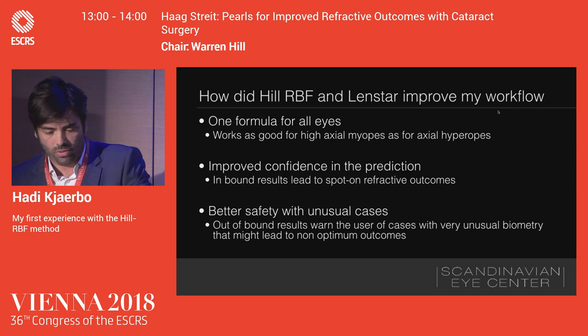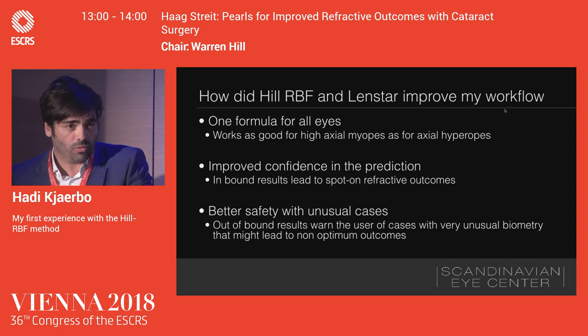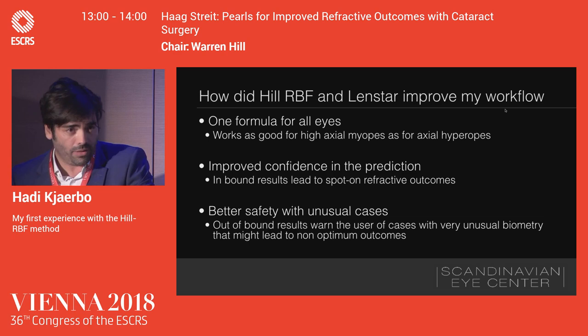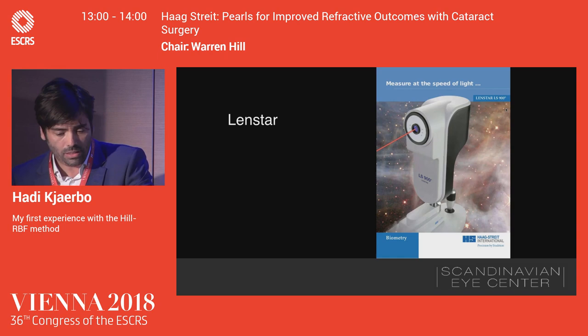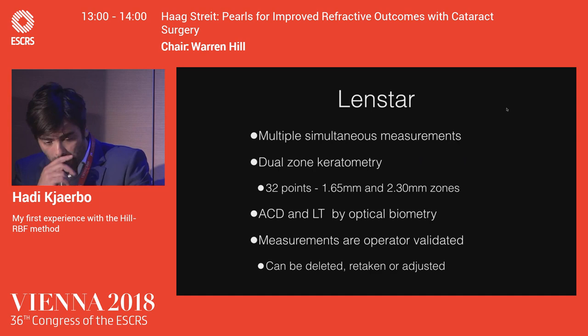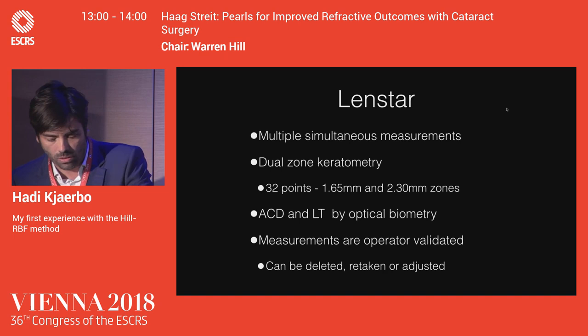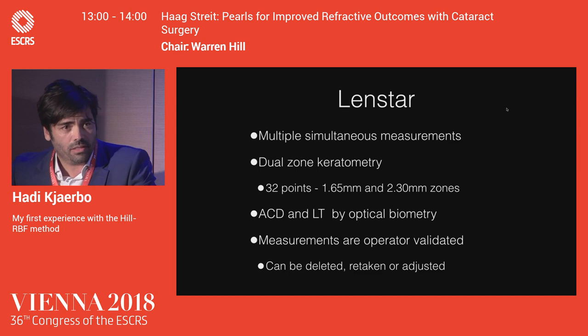How did the Hill-RBF and the LensStar improve our workflow in the clinic? Well, it's one formula for all eyes. We have improved confidence in the prediction. Inbounds results give us very good refractions. We have better safety because we can be more aware of the unusual cases. Regarding the biometer, I'm really happy using the LensStar. With one click, you get multiple simultaneous measurements. You have dual-zone keratometry — 32 points in two separate rings — one in the 1.65 mm zone and one in the 2.3 mm zone. Very precise optical biometry, and the measurements are operator-validated, making the system very flexible.